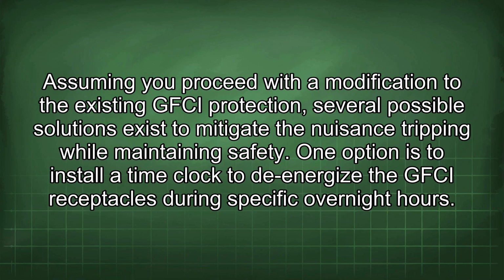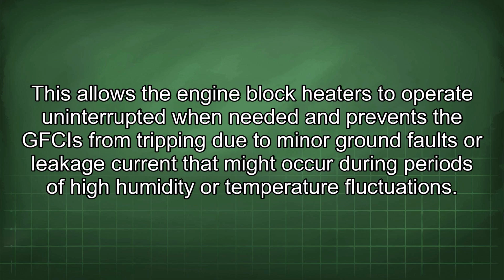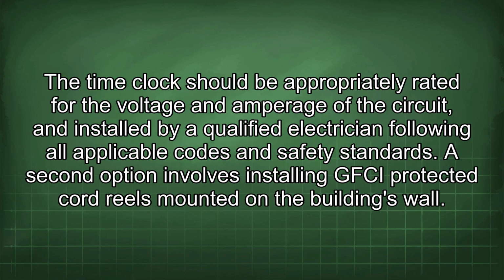Assuming you proceed with a modification to the existing GFCI protection, several possible solutions exist to mitigate the nuisance tripping while maintaining safety. One option is to install a time clock to de-energize the GFCI receptacles during specific overnight hours. This allows the engine block heaters to operate uninterrupted when needed and prevents the GFCIs from tripping due to minor ground faults or leakage current that might occur during periods of high humidity or temperature fluctuations. The time clock should be appropriately rated for the voltage and amperage of the circuit and installed by a qualified electrician following all applicable codes and safety standards.